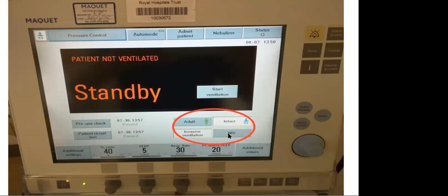Then you have to choose which type. Is it an invasive or non-invasive type? Okay. So once you choose that, you will see this is an infant mode and it's invasive. So you can see here in the left corner, it's showing an infant. And if you want to change between invasive and non-invasive ventilation, the ventilator must be returned to the standby screen, by pressing the power button in the lower left hand corner. You can see here the power button is there. By pressing that you can change between invasive and non-invasive.